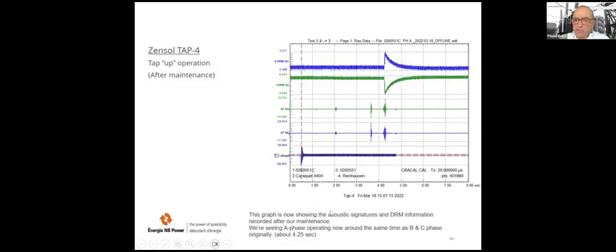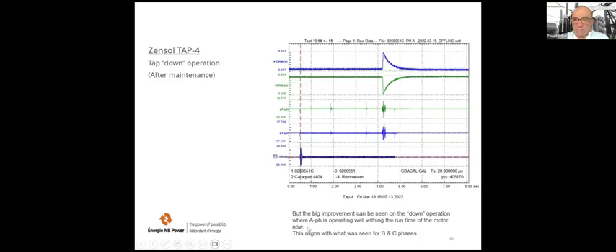This graph is now showing the acoustic signatures and DRM information recorded after our maintenance. We're seeing A phase operating now around the same time as B and C phase, about 4.25 seconds. But the big improvement can be seen on the down operation, where A phase is operating well within the runtime of the motor now. This aligns with what was seen for B and C phase.